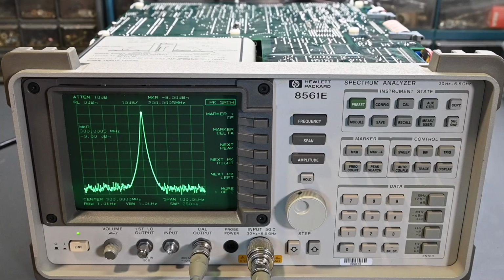So it looks like the low band is working, and that really does confirm that the other module is faulty. So perfect, excellent, good start on here. So let me do this. The next thing is actually we need to set the reference level adjust before we do any other calibrations.